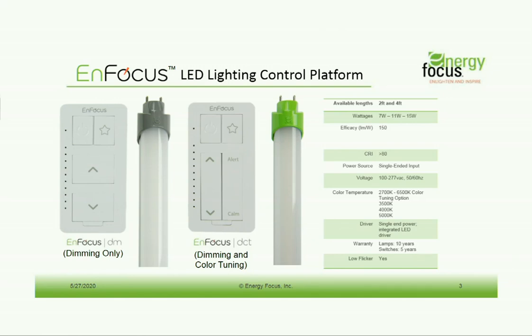This will be a single-ended power, internal driven. This is not any external driven requirement, you know, backup system to support this solution, this platform. It is 100 to 277 volt. And one of the biggest features here is the range of dimming and the range of color tuning. You have 10 different levels of dimming, and then also a range of color tuning from 2700K to 6500K. That is a significant range, and I think will meet pretty much any customer's needs.